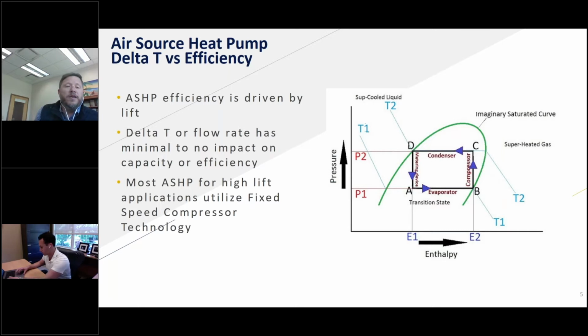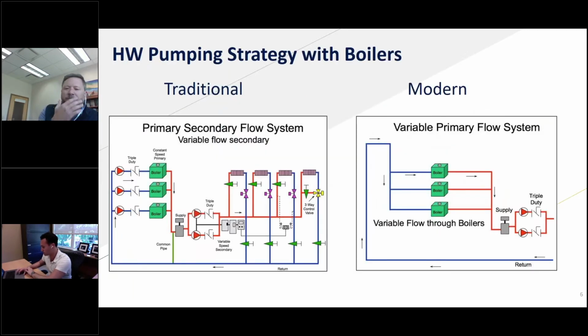So moving on from just looking at the heat pump or the boiler itself and how we drive efficiency at the boiler level, we also look at, as I said, with those delta Ts, how are we going to pump the water through the building? If we think about a historical thought process on where we came from to where we are today, boilers, no different than chillers from previous generations, were designed and optimized for constant flow from a water flow perspective.